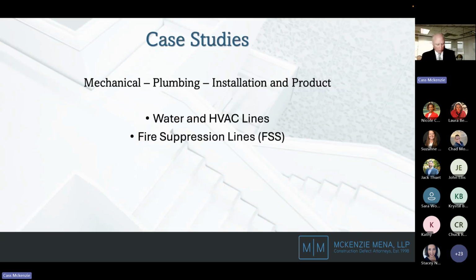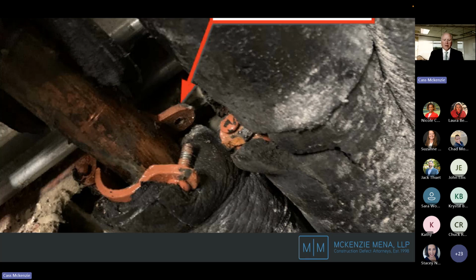So what are some of the things we've seen as we go through these cases? I think the biggest one right now is mechanical and plumbing installation and product issues with certain water lines, HVAC lines, and especially the fire suppression system lines. With these buildings, you're pumping a lot of water, electricity, and coolant up and down, with large vertical runs of piping that has to be installed a certain way to handle the weight and capacity of the building. What we've noticed a lot is that the support systems for the piping simply aren't up to commercial grade—the pipes are too heavy for the supports installed, they fail, and push the pipes away. This is a copper refrigerant pipe carrying cooling for HVAC systems, which I'll talk about in a minute.